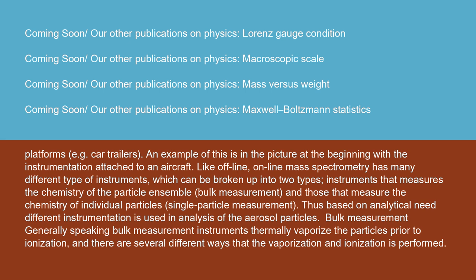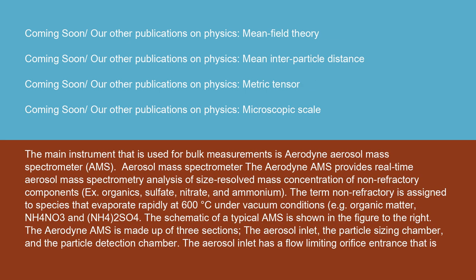The main instrument used for bulk measurements is the Aerodyne aerosol mass spectrometer (AMS). The Aerodyne AMS provides real-time aerosol mass spectrometry analysis of size-resolved mass concentration of non-refractory components, including organics, sulfate, nitrate, and ammonium. The term non-refractory is assigned to species that evaporate rapidly at 600 degrees Celsius under vacuum conditions, such as organic matter, NH4NO3, and (NH4)2SO4. The Aerodyne AMS is made up of three sections: the aerosol inlet, the particle sizing chamber, and the particle detection chamber.